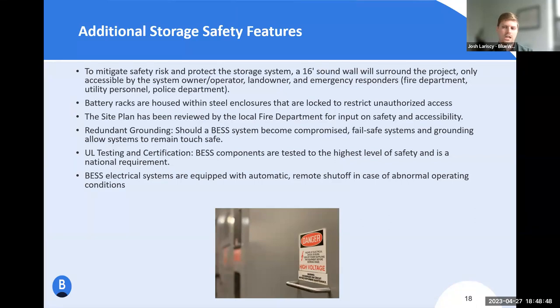Another key component is that the system is always monitored 24/7 remotely by Blue Wave, and likely also redundantly by the manufacturer. That's monitoring temperature, voltage, and any conditions on the site. If the door on one of the enclosures opens, we will know about it immediately. The system is automatically triggered to shut off remotely on its own if an alarm is triggered or any abnormal conditions are detected. Blue Wave would also have the capability to shut off the system remotely at any time.